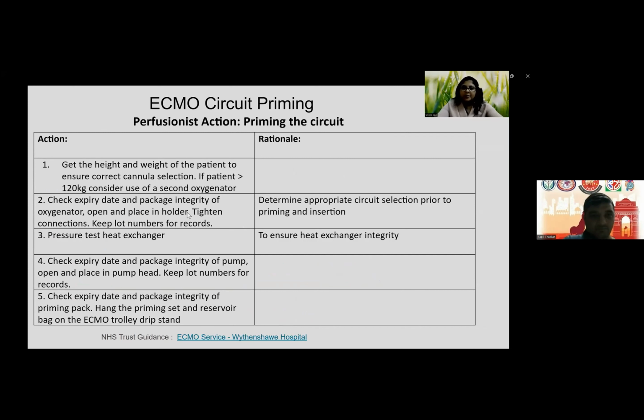Check the expiry date and the package integrity of the oxygenator, and open and place it in the holder of the ECMO pump, and tighten the connections. Keep a lot number for the records, right? So this helps in determining the appropriate circuit selection prior to priming and insertion. Pressure test the heat exchanger to ensure the heat exchanger integrity. Check the expiry date and package integrity of the pump, and open and place it in the pump head. Keep lot numbers for record.